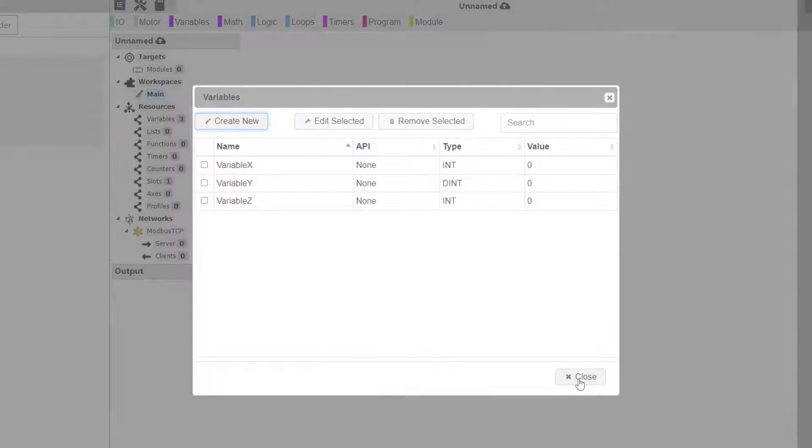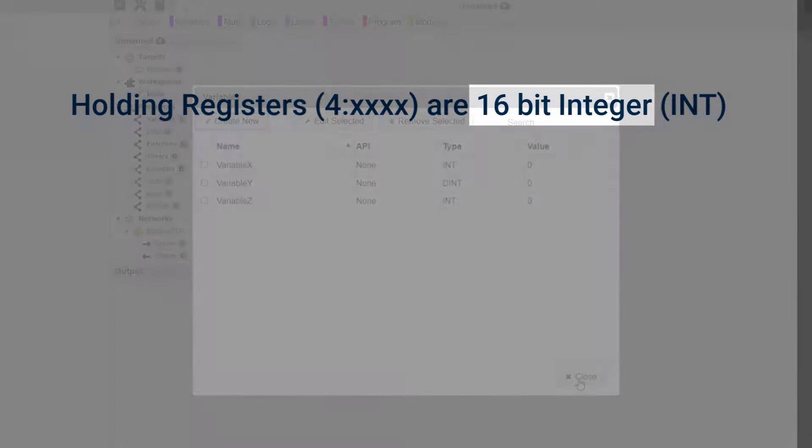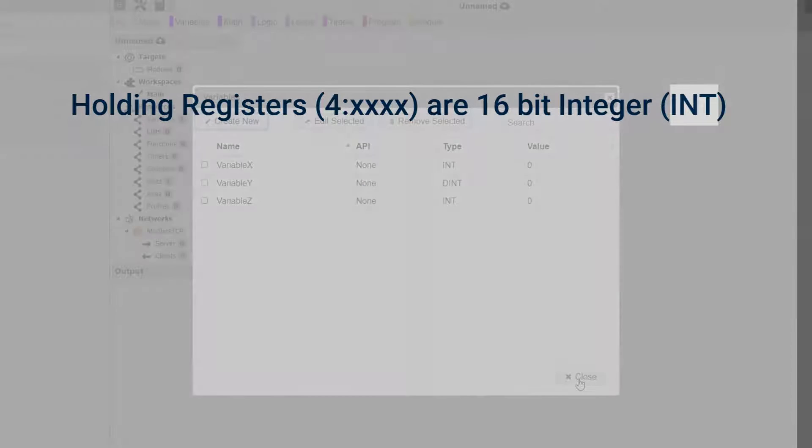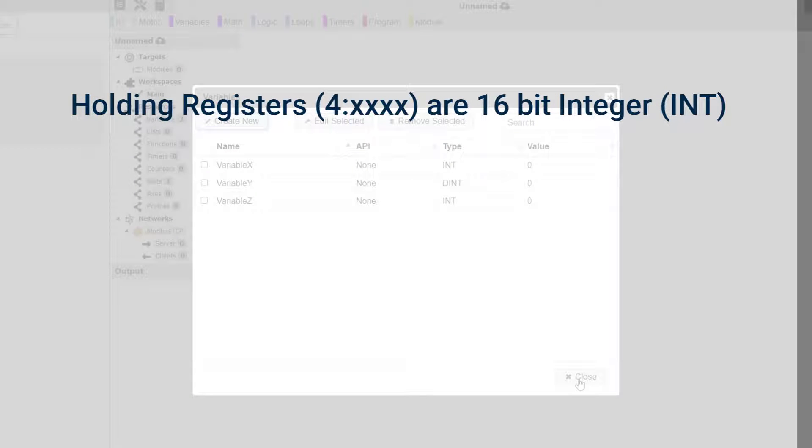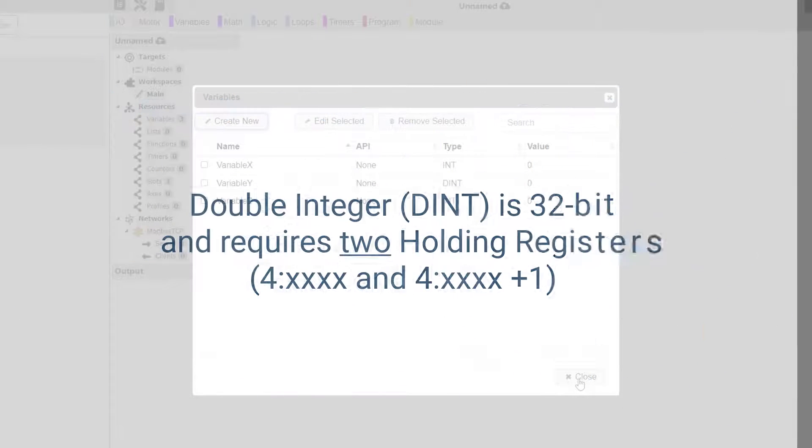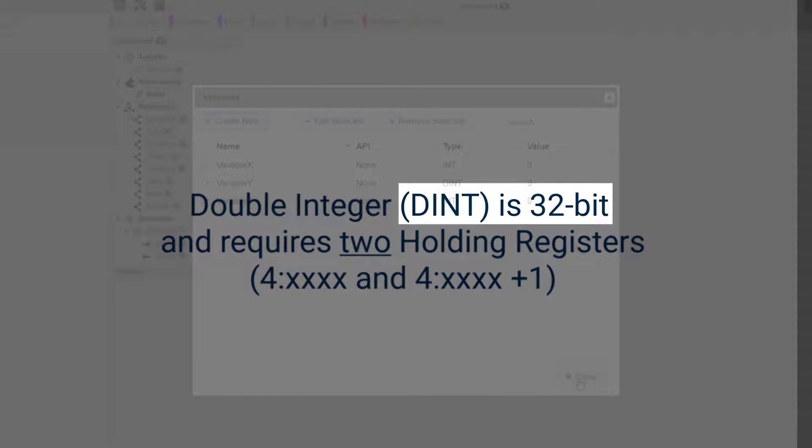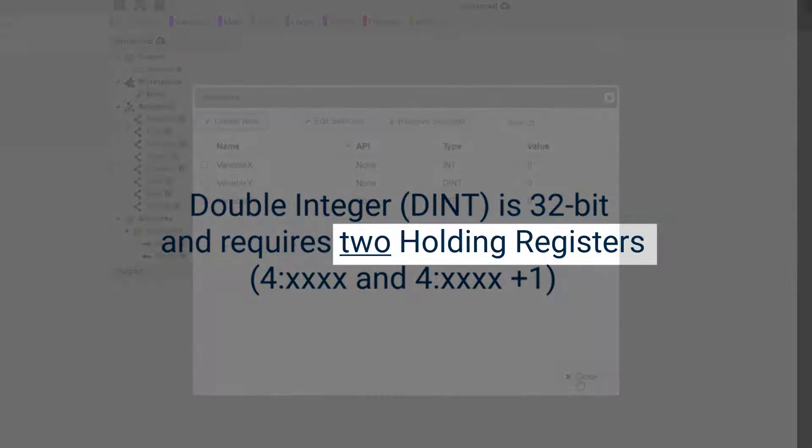Please also note that Modbus holding registers are integer based. If we are assigning a variable with an integer data type, then the variable will utilize one holding register. If our variable is of a double integer data type, it will require two holding registers.